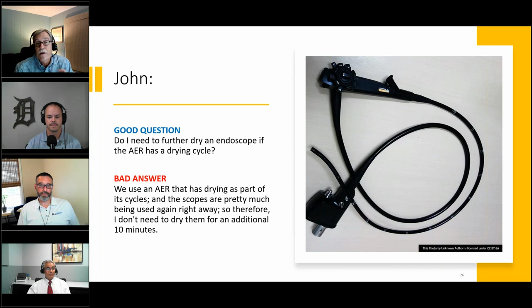Next slide, please, Seth. So endoscope drying after processing has gained increased attention in the last several years, both because of research and clinical investigations that have shown the real reality of residual moisture, especially for channeled endoscopes. It's not been uncommon when we perform our site visits to see scopes hanging in storage, still wet on the outside, and not uncommonly dripping water onto the floor of the scope cabinet. So we really need to change the mindset that these are red flags. Residual moisture allows an environment that's favorable to bacterial proliferation and biofilm development.